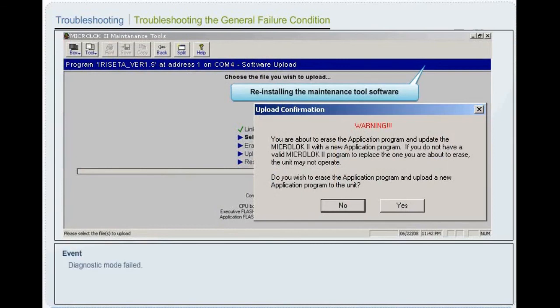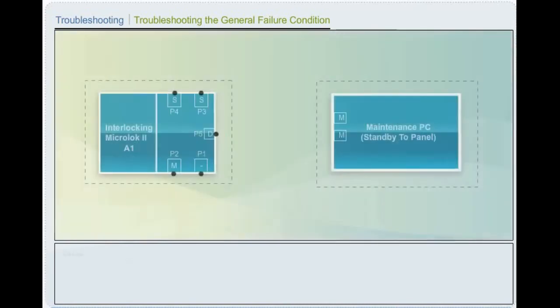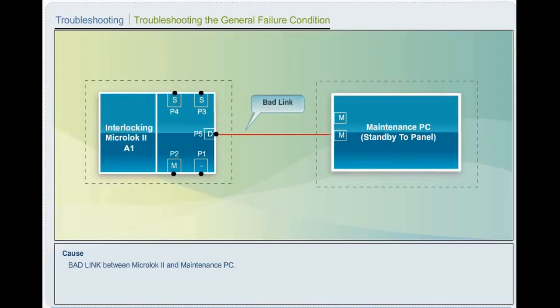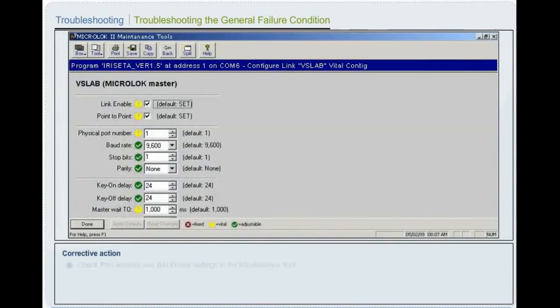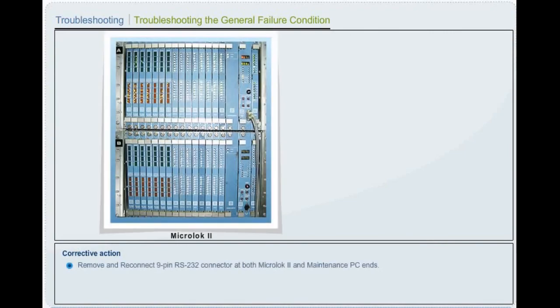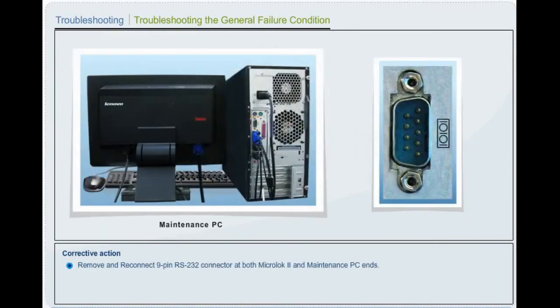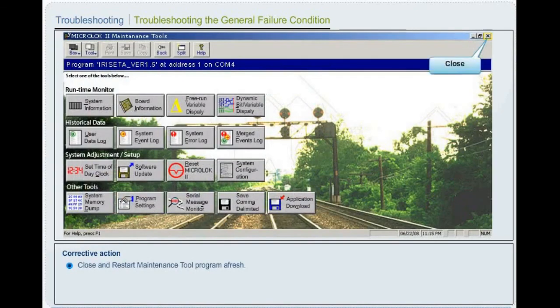Event: Diagnostic mode failed. Cause: Bad link between Microlok II and maintenance PC. Corrective action: Check port address and baud bits per second rate settings in the maintenance tool. Remove and reconnect 9-pin RS-232 connector at both Microlok II and maintenance PC ends. Close and restart maintenance tool program afresh.